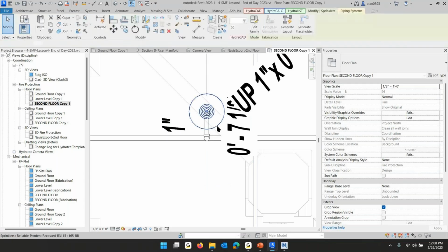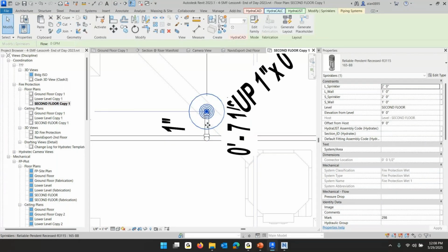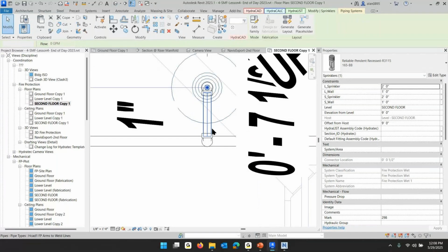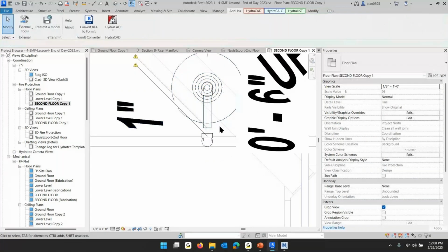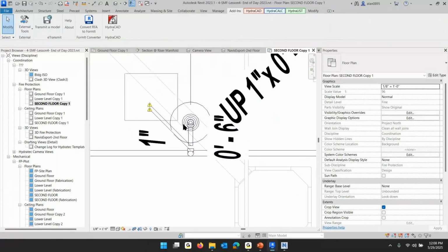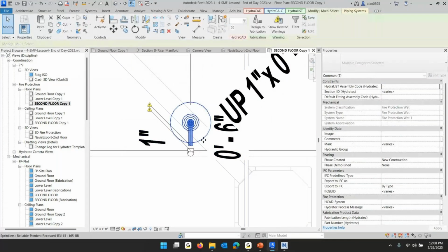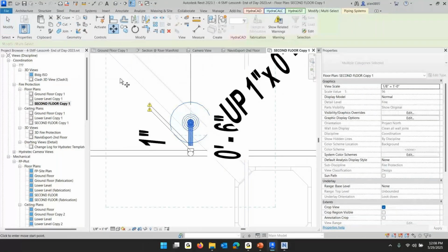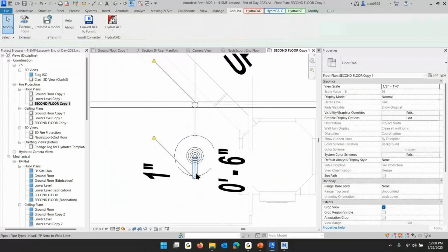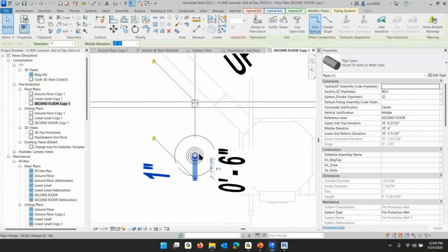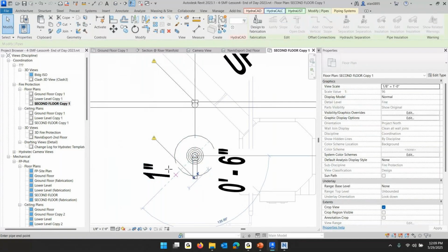head 2 feet south, this pipe's going to try and get shorter, and it can't get shorter than 0. So then it's going to yell at me. Rather than let it yell at me, I'm going to disconnect it. And then I'm going to pick a window around it. So I've got the sprinkler and the drop and the elbow and the other thing, and I'm going to move that from any old place pointing south, go 2 feet. Now Revit will let me take an unfixed piece of pipe that's at an elbow and rotate it any way that I want.